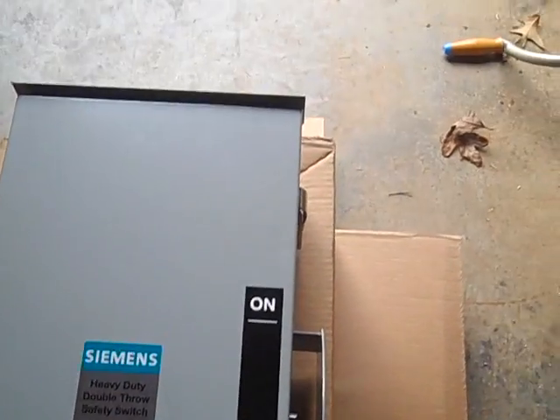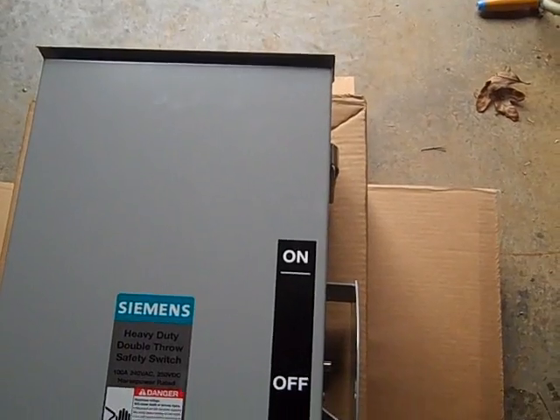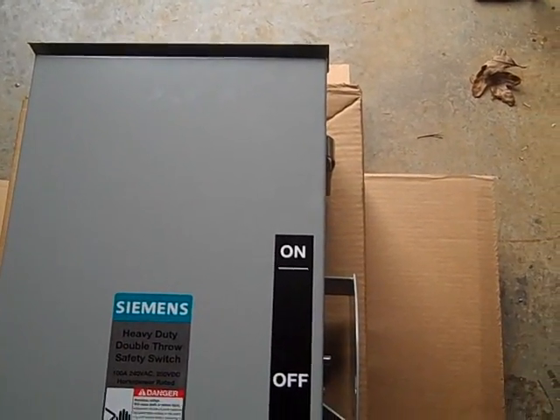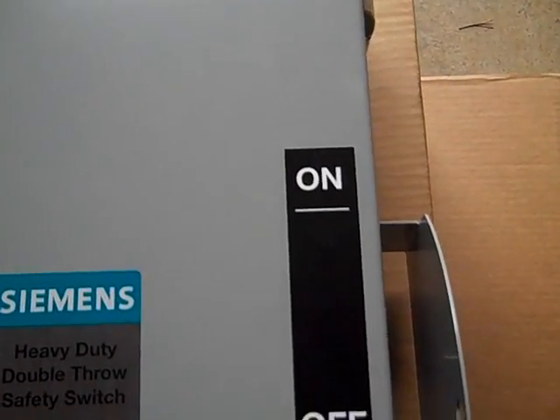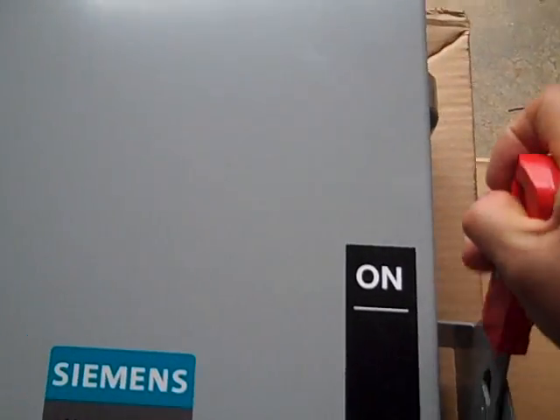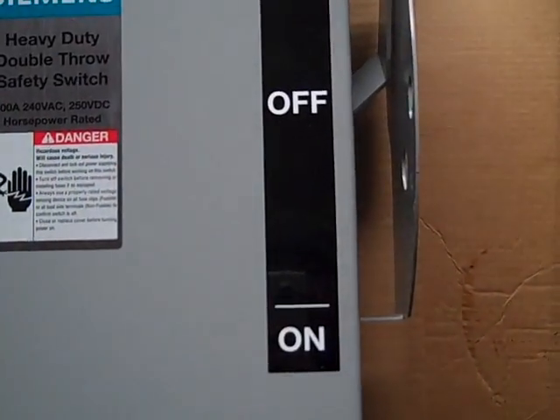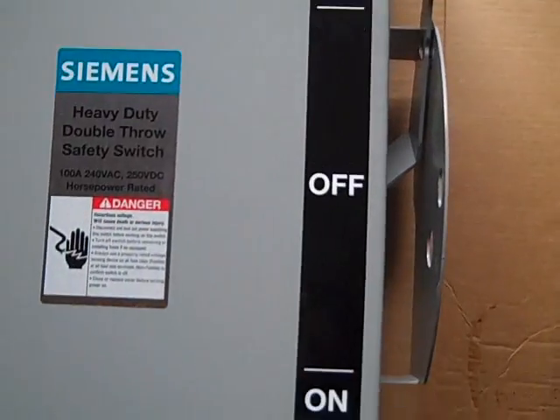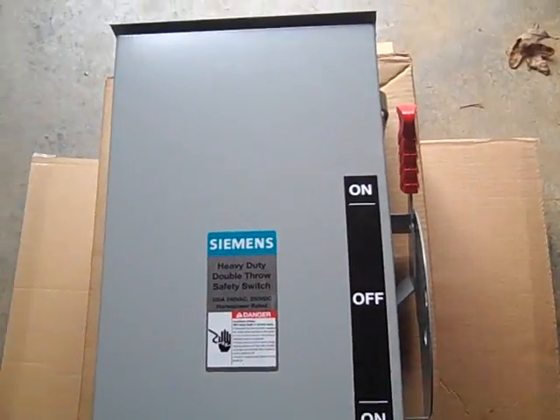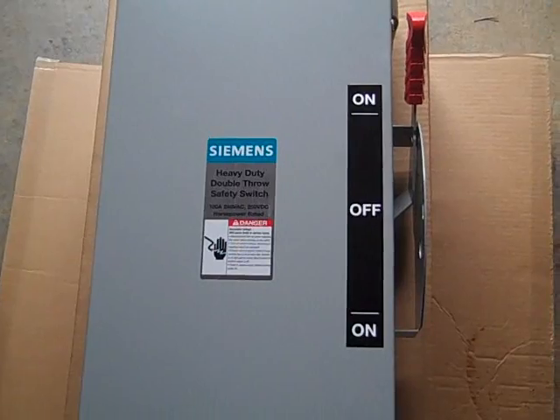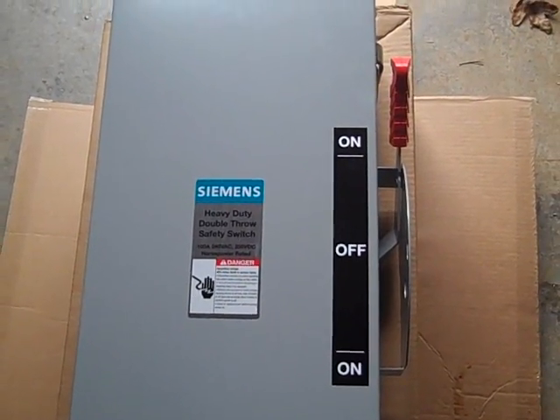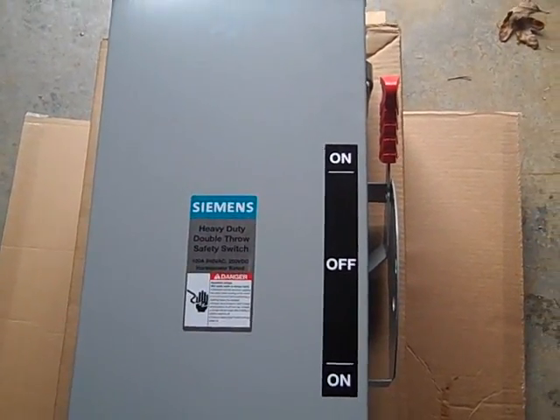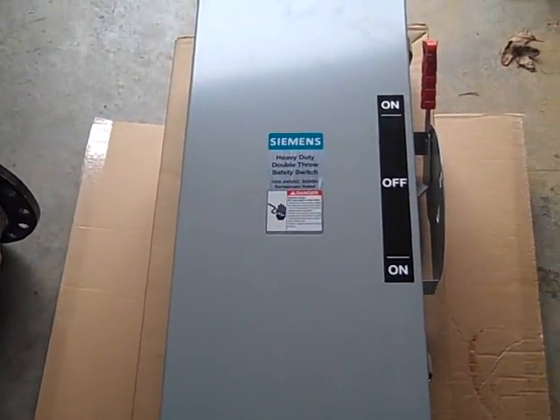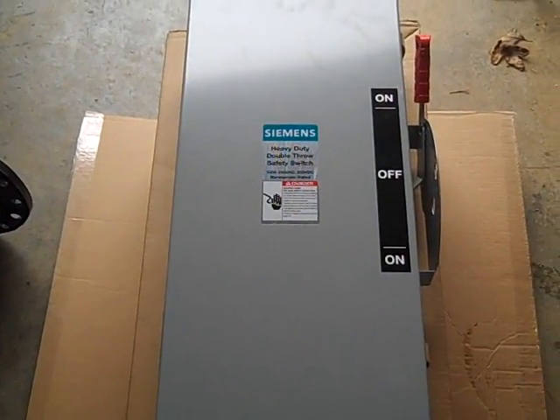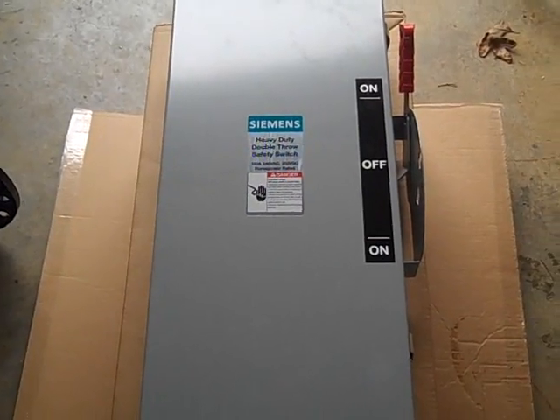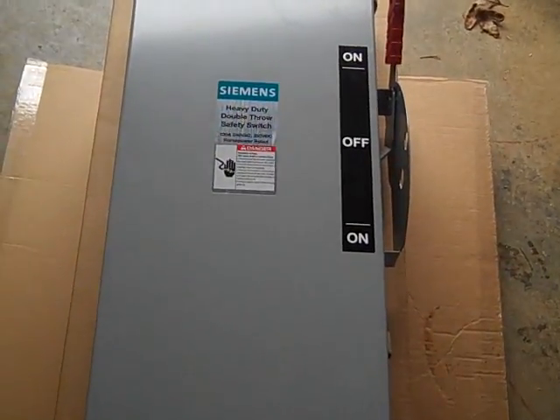That would allow me to reload the wood gas generator if I had to, run for another 2 hours, get the wood gas generator going, and then switch back to it, and vice versa, or any other scenario we might run into, or just for maintenance purposes with one generator. So between the two transfer switches, I should be able to run off the grid on 2 generators and switch back and forth with some pretty good heavy-duty switchgear.